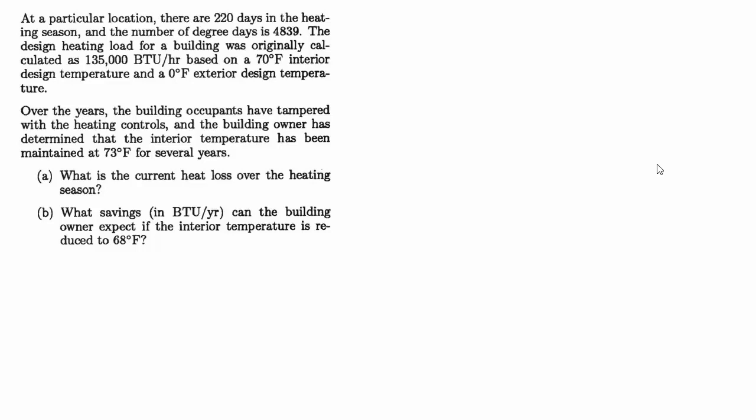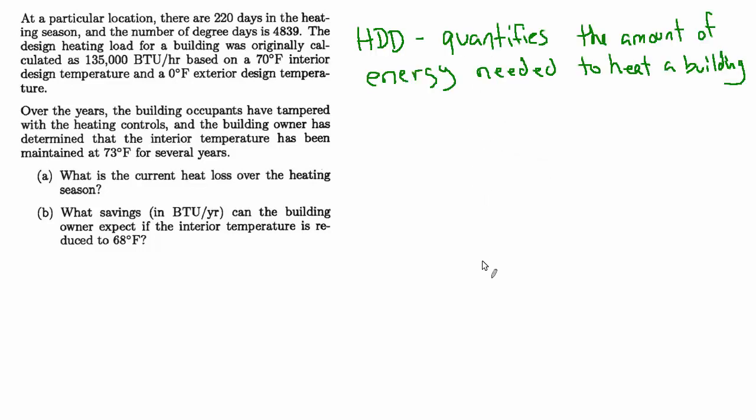So let's start with a reminder of what heating degree days are. Heating degree days is an attempt to quantify the amount of energy needed to heat a building. So how does that work? To actually calculate that, what they do is for each day, they take the difference between a base temperature and the average temperature outside.